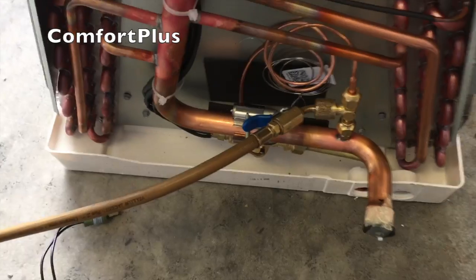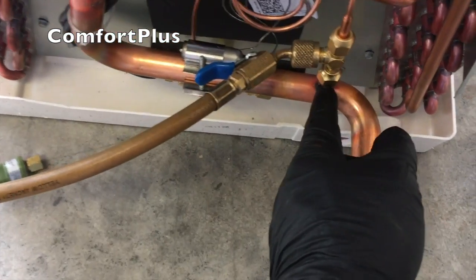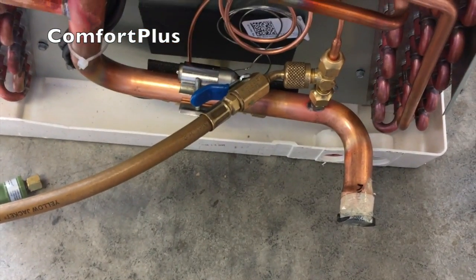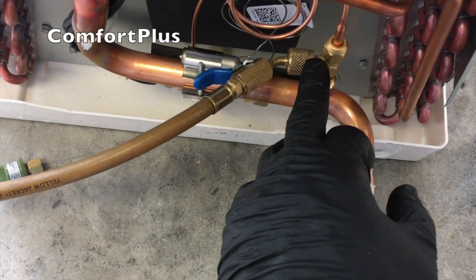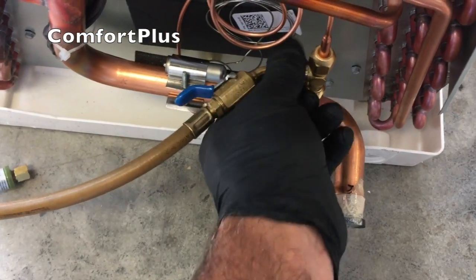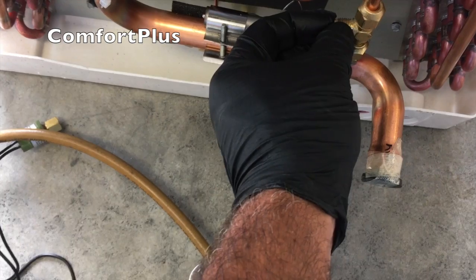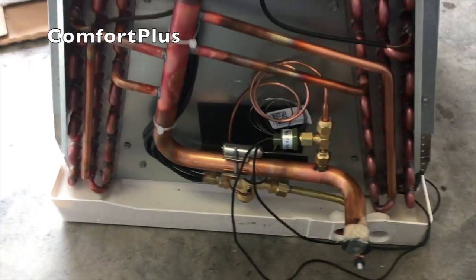Okay, I'm putting a little nitrogen back in the coil. Of course, it'll let the holding charge off of it when I remove the equalizer. I've got a valve core in this particular port, so it'll hold the nitrogen in until I can get the pressure switch screwed back on. And there we have it.